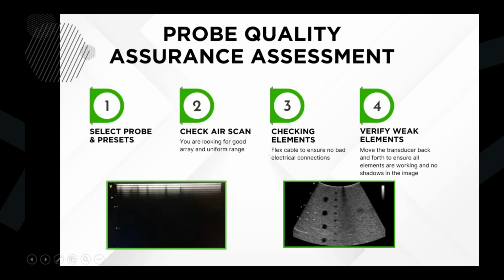Over here on the right-hand side, if you saw some dropout and you put it on your phantom, this is what the dropout would look like on a particular phantom. Go over here to 2D. I think I got this one over here. All right, this is the air scan of our 12L linear transducer. You can see for this one, I would drop down the depth, and can increase the gain. You want to make sure that you have uniformity across the image. You can see that there's no dropouts like there were in the other picture over there.